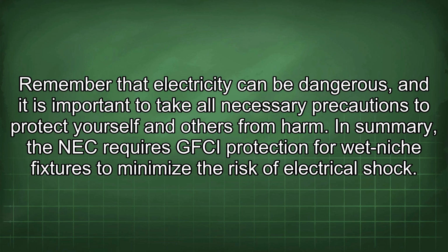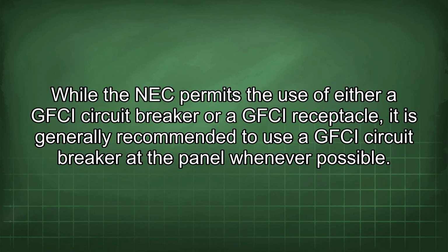from harm. In summary, the NEC requires GFCI protection for wet niche fixtures to minimize the risk of electrical shock. While the NEC permits the use of either a GFCI circuit breaker or a GFCI receptacle, it is generally recommended to use a GFCI circuit breaker at the panel whenever possible.